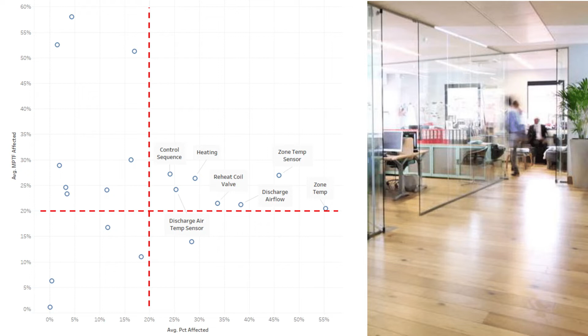Look at the quadrant again in terms of what's happening most commonly. We again have 7 faults showing up in that top quadrant, more than 20% of units, more than 20% of the time. There isn't really a strong trend. For the air handlers, 4 out of the 7 were supply air related. In this case, we have a couple that are zone related, a couple to do with discharge air. I think that's just the general trend here.